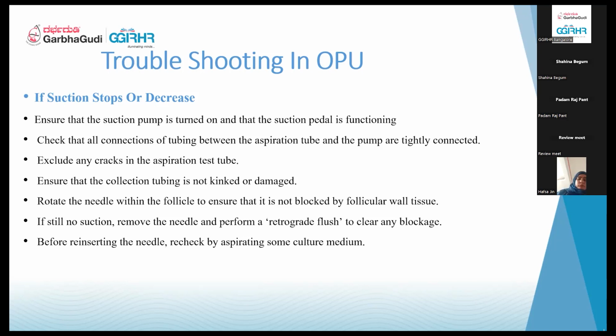Next, you will see whether there are any cracks in the test tubes. If the test tubes have very minute cracks, at times they might go unnoticed. In such cases, everything is fine: your tubings are fine, the suction apparatus is fine, the needle tip is well within the follicle, yet no aspiration takes place. It could be because of those cracks, there is no airtight vacuum, and because of that you're not aspirating the fluid. Then you just change the test tube and discard that cracked test tube.